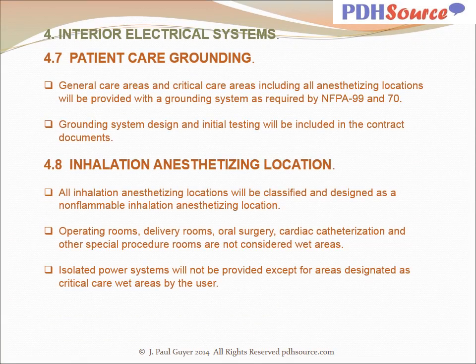General care areas and critical care areas, including all anesthetizing locations, will be provided with a grounding system as required by NFPA 99 and 70. Grounding system design and initial testing will be included in the contract documents. All inhalation anesthetizing locations will be classified and designed as non-flammable inhalation anesthetizing location. Operating rooms, delivery rooms, oral surgery, cardiac catheterization, and other special procedure rooms are not considered wet areas.